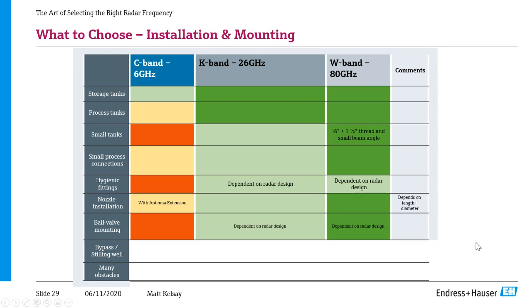Next is ball valve mounting. This goes along the same lines as nozzle installation, but with higher frequency radars in that W band, we are able to very easily mount right on top of a full port ball valve and measure through it down into the tank and get the level. What that allows you to do is, if you've got an application or a process that's critical that you don't want to ever shut down, you can isolate that radar with a ball valve. That way you can close off that ball valve, do any maintenance, repair, swap out that radar device without having to shut down your process.